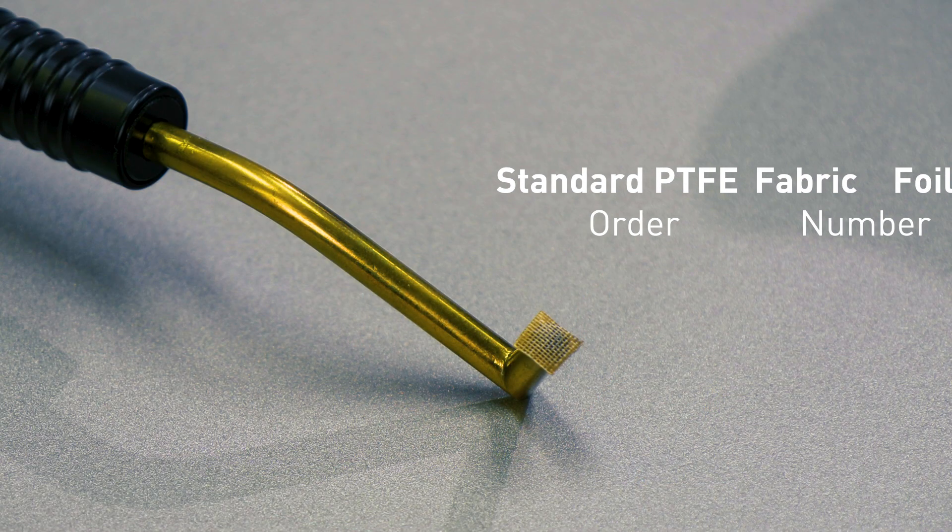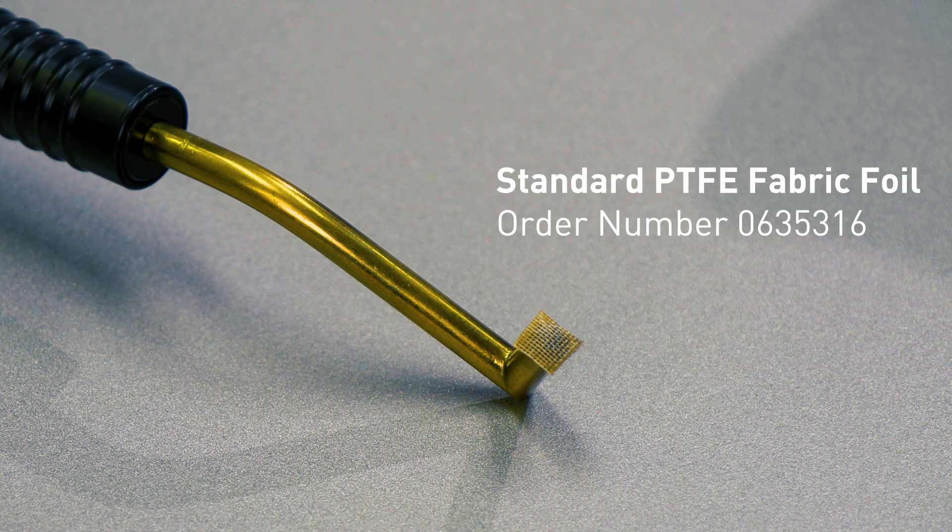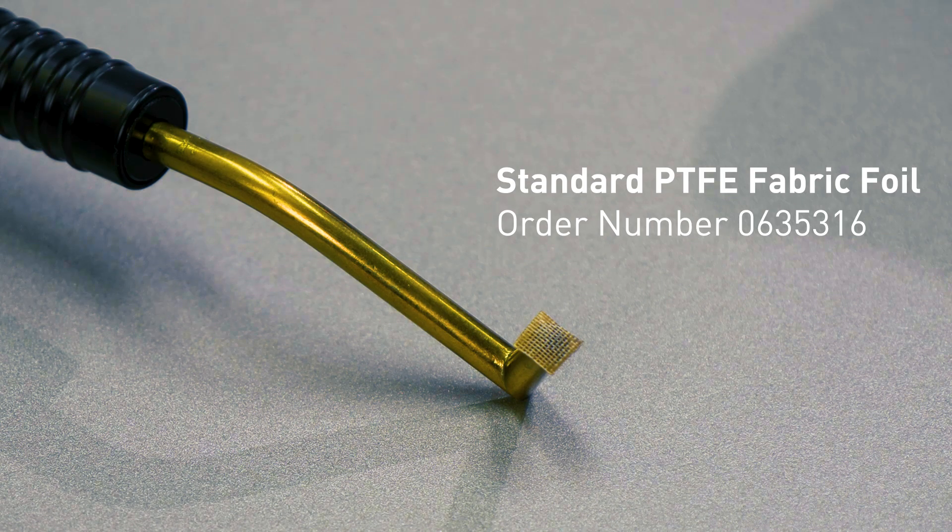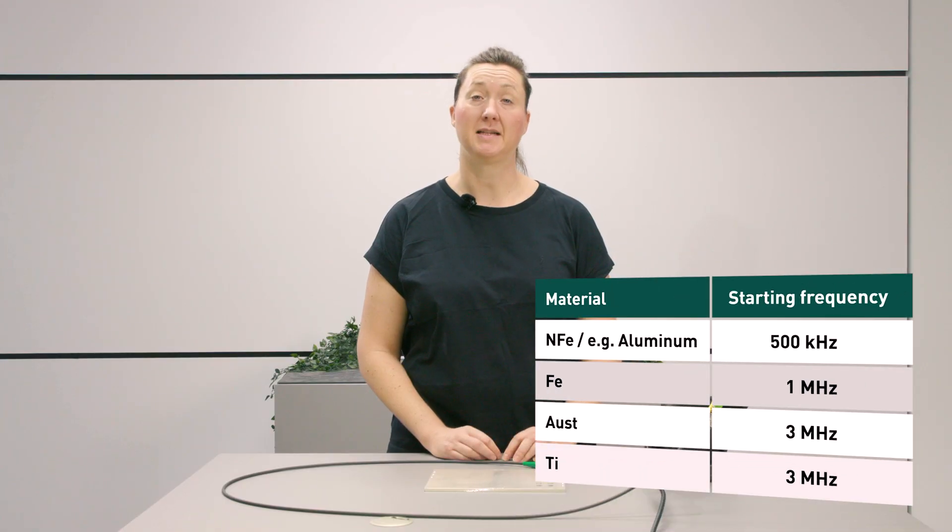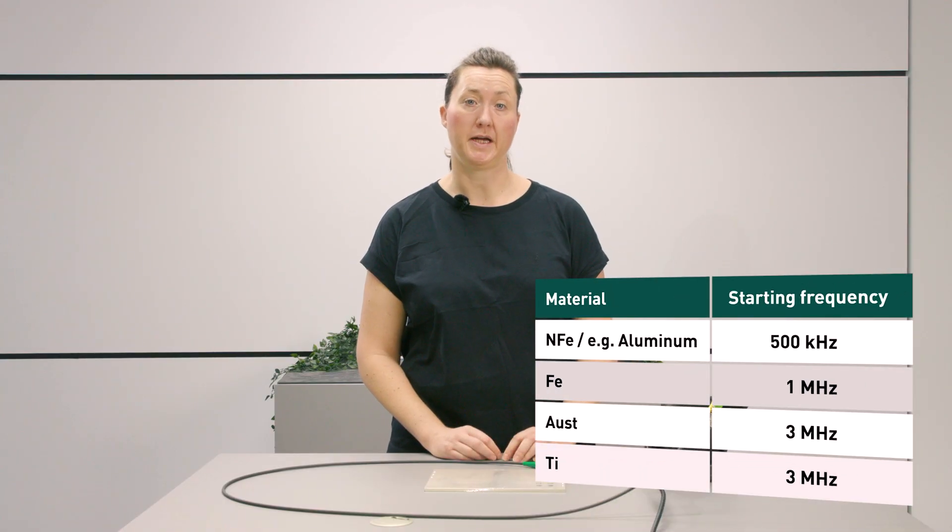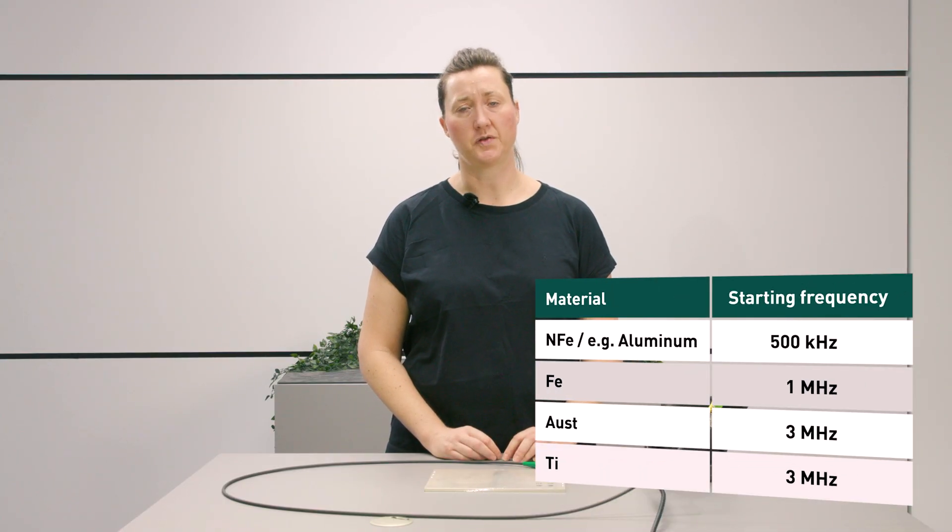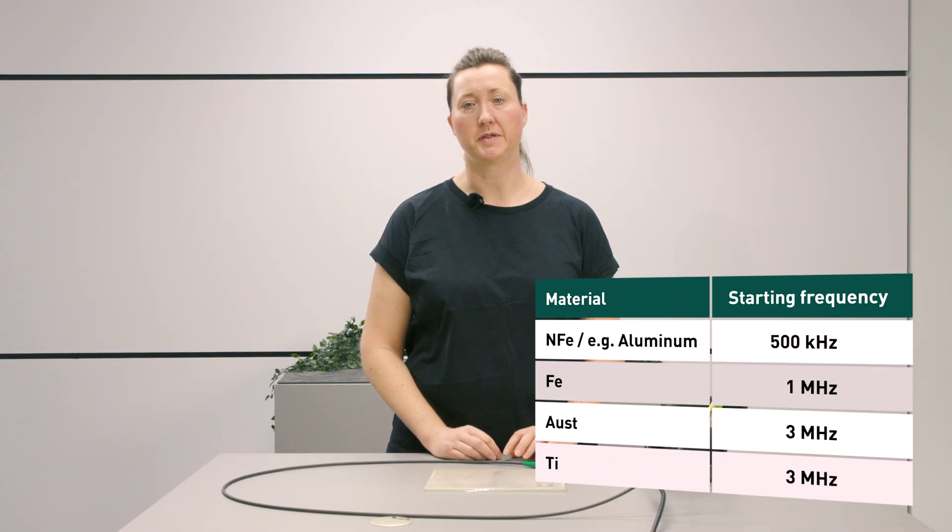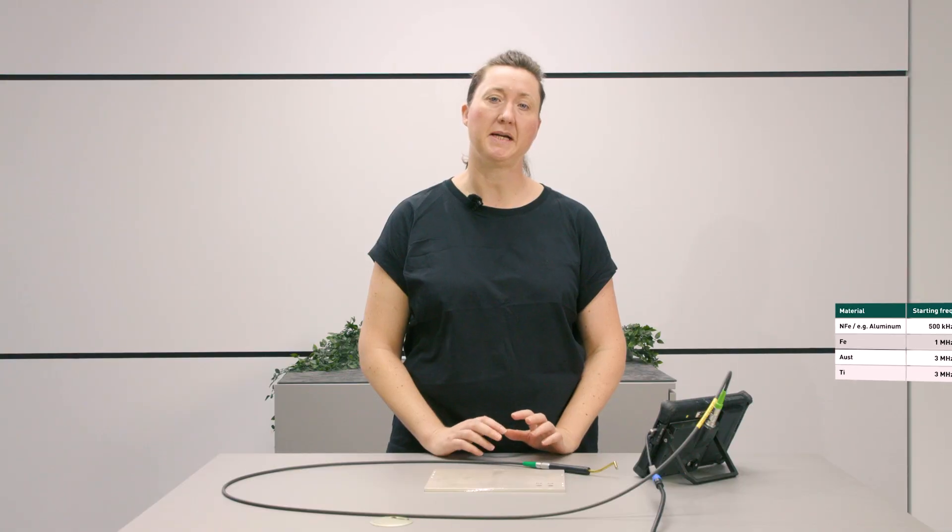To protect the probe, we recommend using a self-adhesive PTFE foil. Now I set up the testing setup correctly. For optimal adjustment of the eddy current signal, we recommend using the following frequencies as a starting point for eddy current testing. This does not represent the optimal solution, but it serves as a solid starting point.